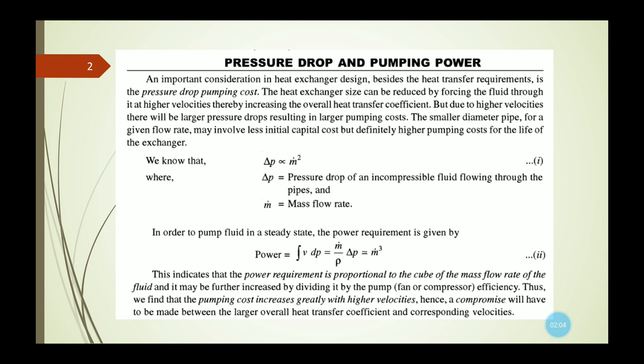Now, if we force the fluid through the heat exchanger at higher velocity, in that case the overall heat transfer will increase for the heat exchanger. But what happens then? Due to the higher velocity of the fluid through the heat exchanger, there will be a larger pressure drop and it results in a larger pumping cost. Now, the smaller diameter pipe for a given flow rate may involve less initial capital cost but definitely higher pumping costs for the life of the heat exchanger.